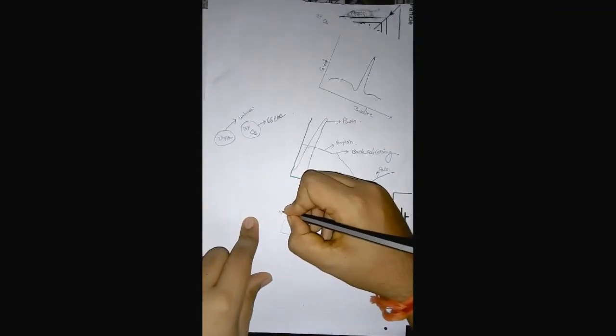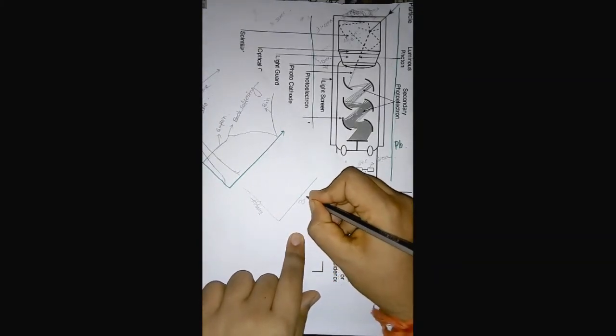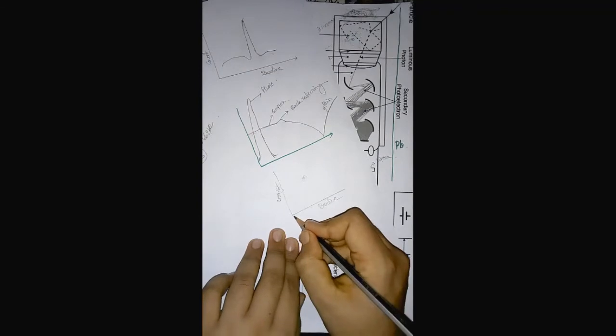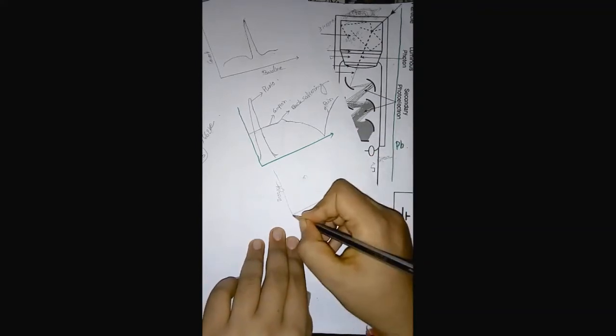All right, and so I have to make my calibration curve, where this part will be energy and this will be my baseline. So I will get the baseline of the peak value, and I have the energy. Let us assume it is here for cesium, and for the calibration curve I know that the straight line will have to pass through the origin, which is 0, 0. So my calibration curve is this, a straight line.